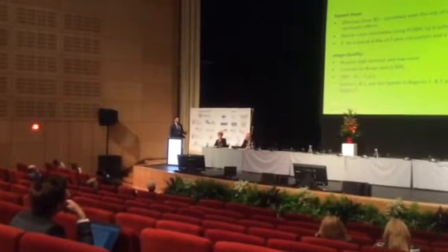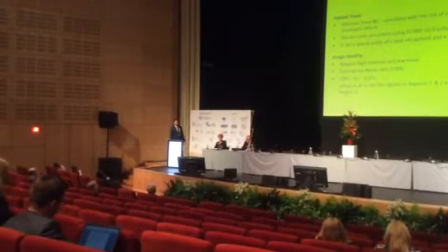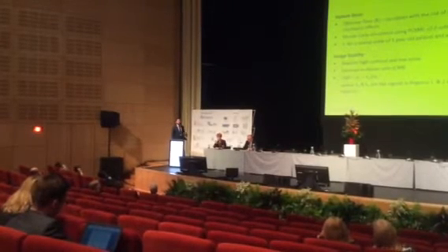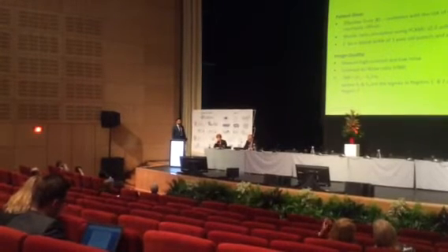So there are a number of ways to define both patient dose and image quality. So prior to initiating the study, I had to decide which two metrics I would use. So the effective dose was the most relevant for patient dose, as it's directly related to the risk of radiation-induced stochastic effects. So I used PCXMC version 2.0, which is a Monte Carlo simulation software package. I computed the effective dose for a lateral ankle of a 1-year-old patient at a range of different beam qualities for a fixed input air kerma.